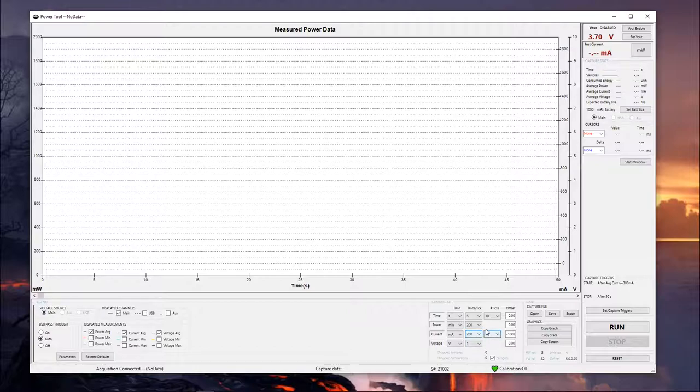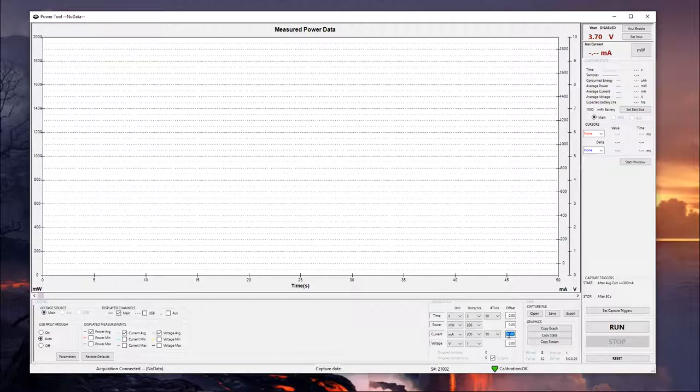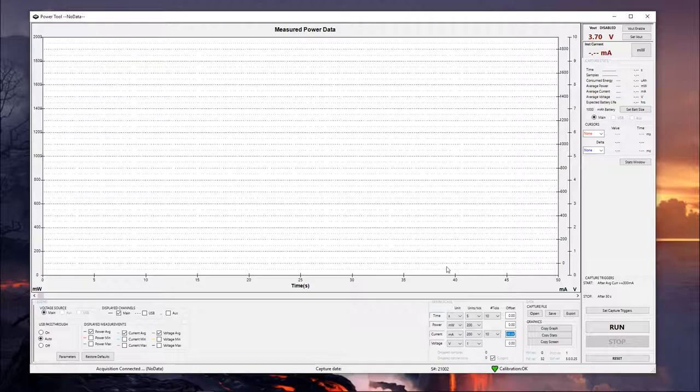And so this is fairly simple. The way I have this set up right now, I actually have an offset of negative 100 on my current, simply because it's easier to see a low current around zero when you've got some buffer below the zero point.